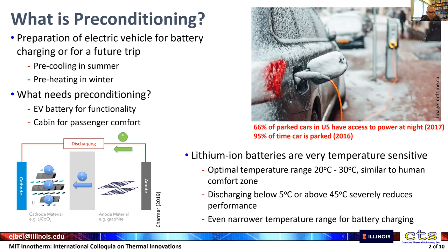When we talk about especially the battery preconditioning, we need to realize that the lithium-ion batteries especially are very temperature sensitive. The optimal temperature range, we already learned, is very close to the comfort zone of humans, somewhere around 20 to 30 degrees C. And if we go to either conditions that are either very much below or very much above, then we can either severely reduce the performance or even permanently damage the battery component. We also realize or experience that the temperature range for battery charging is even more narrow, so that needs to be taken into account when designing these charging systems.